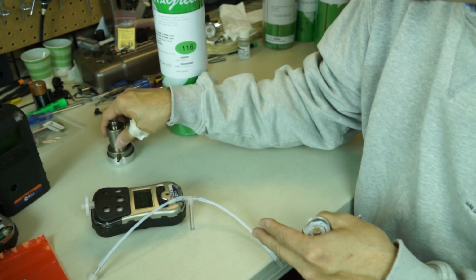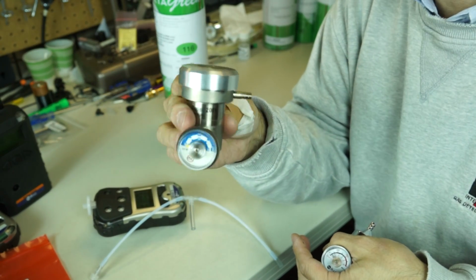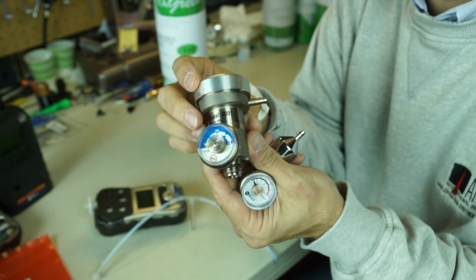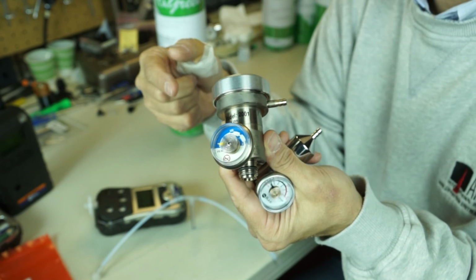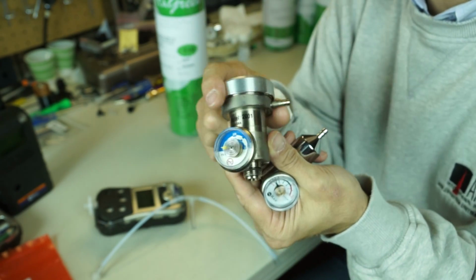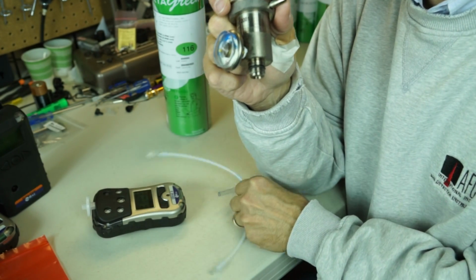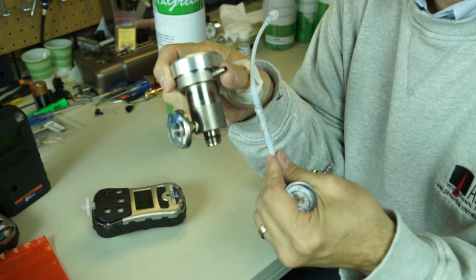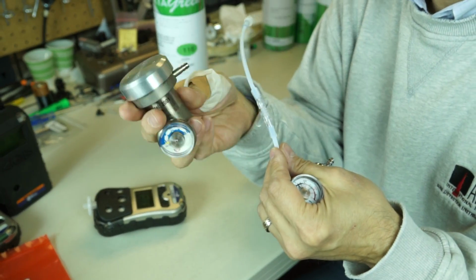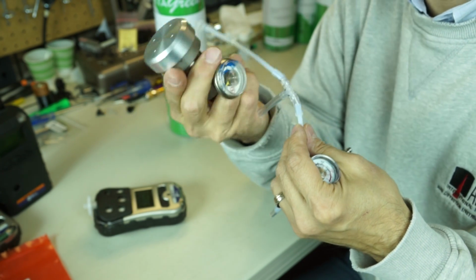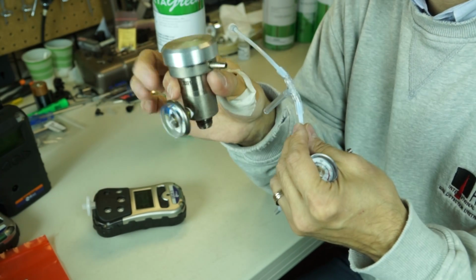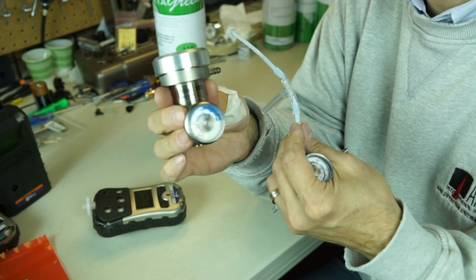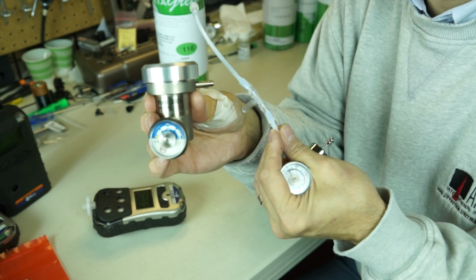Now, you do not want to be using a demand flow regulator with a T. I'm going to mention this because I've seen people do this. A demand flow regulator could be used in lieu of a T. I don't particularly care for them. They put too much back pressure on the sensors, but don't be confused and use a demand flow regulator that you have with another instrument with a Cal T.